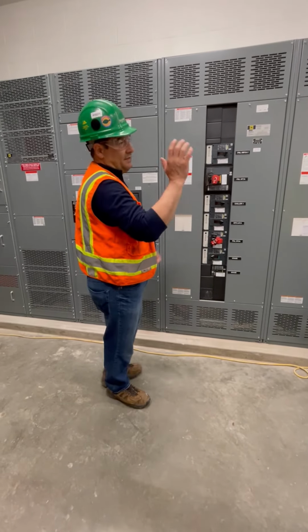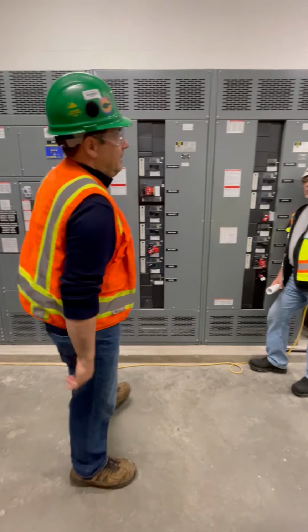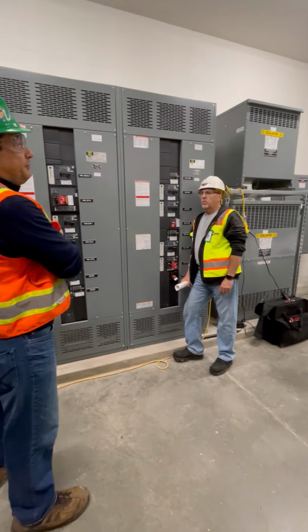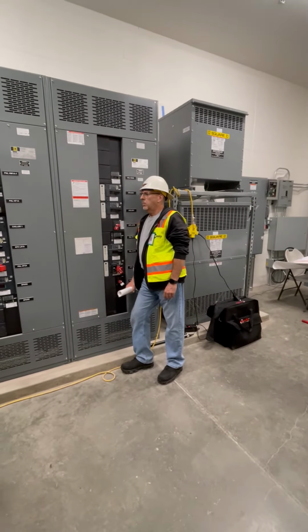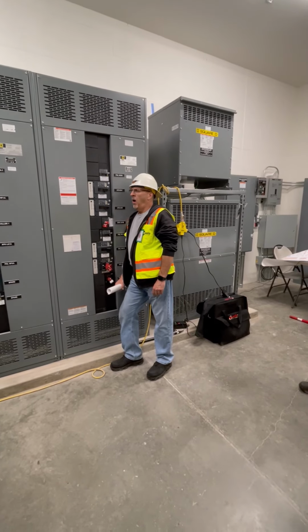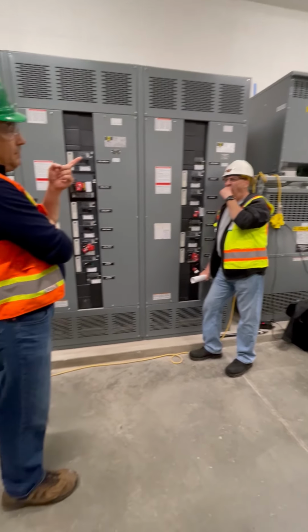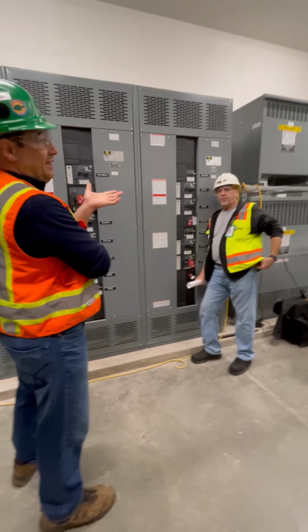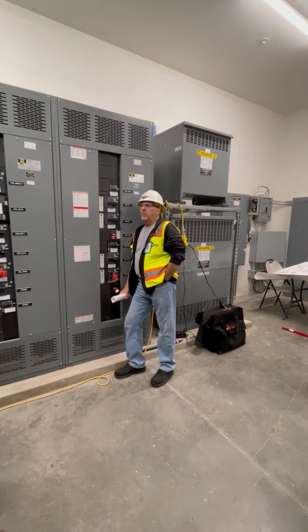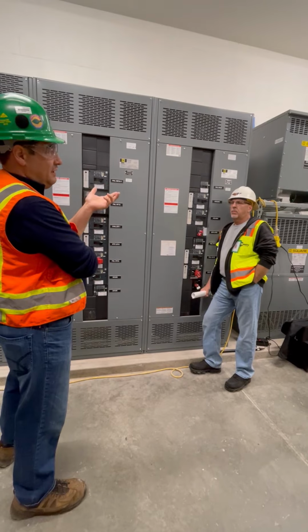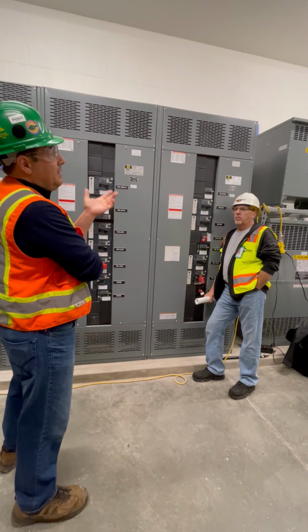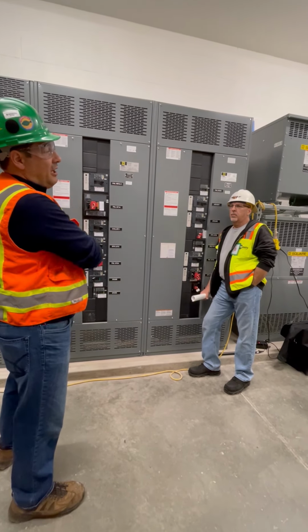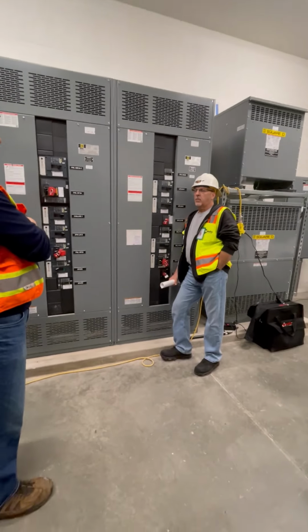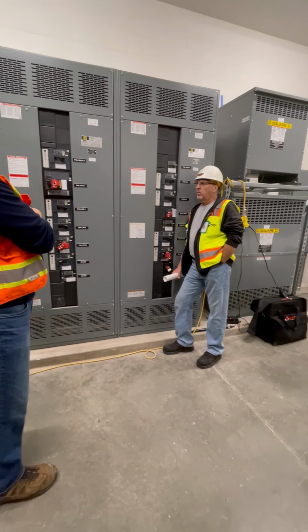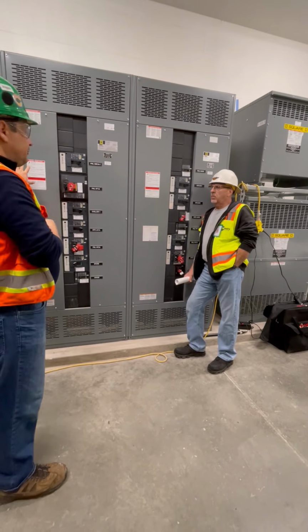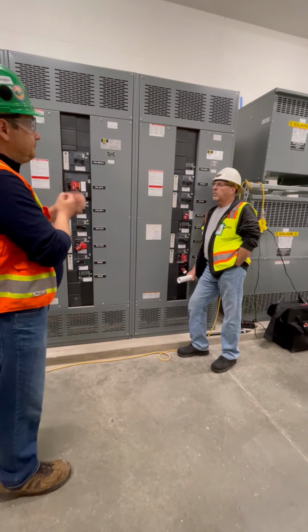But other than that, like I said, on the switchboards and transformers, it's very straightforward. Most people don't touch them, but we still recommend yearly maintenance: check connections, and you can do a megger test and a ratio test on those transformers. Same thing on those transformers, we have rectangular IR windows. Again, if you're looking at putting a program together, those windows may save you, especially on this one, because you cannot take it down, period.